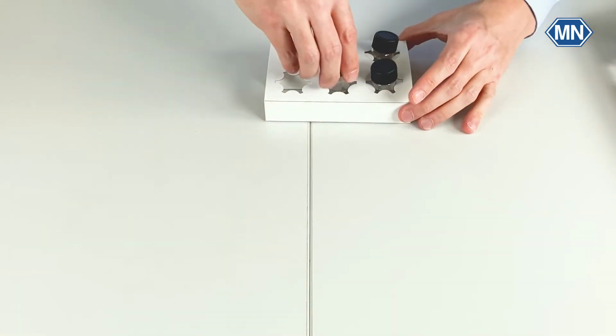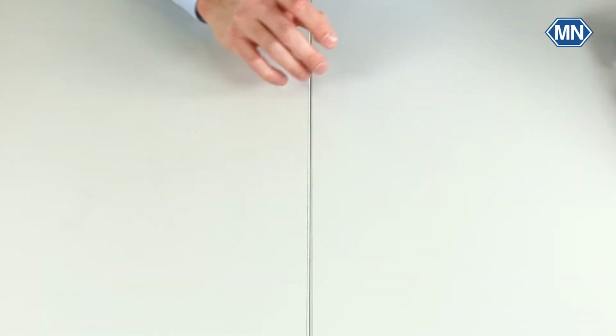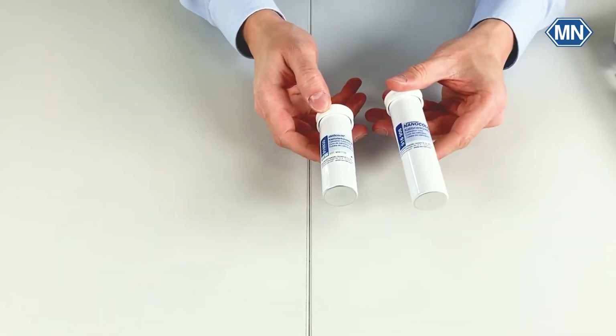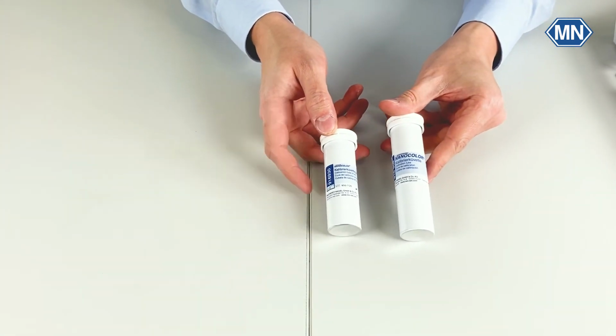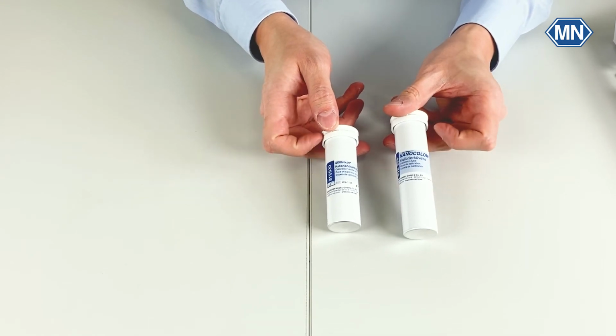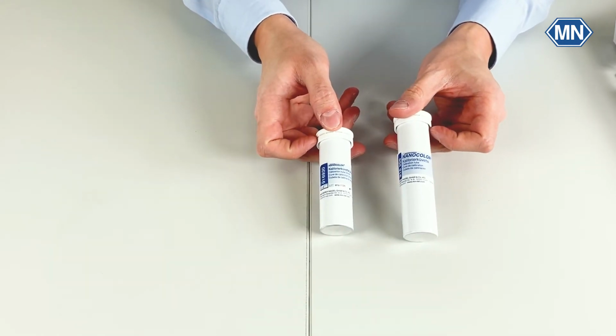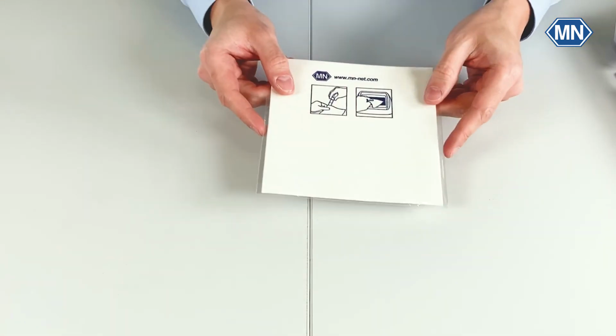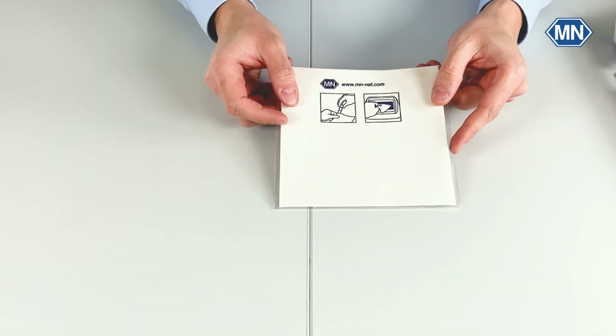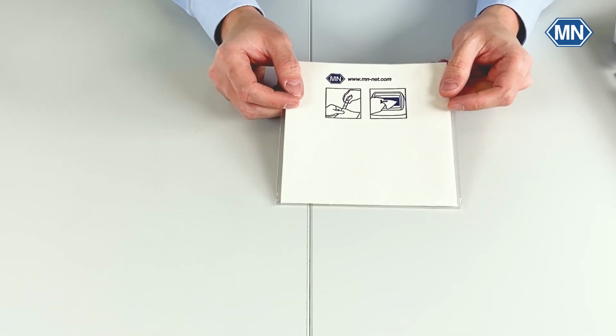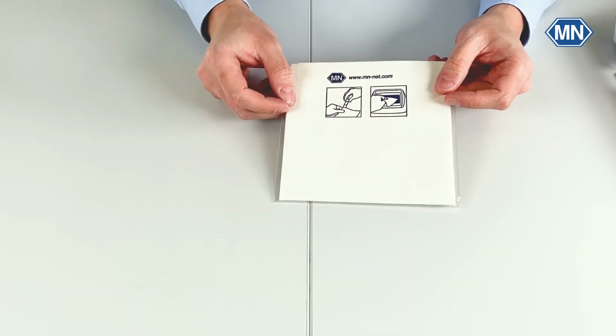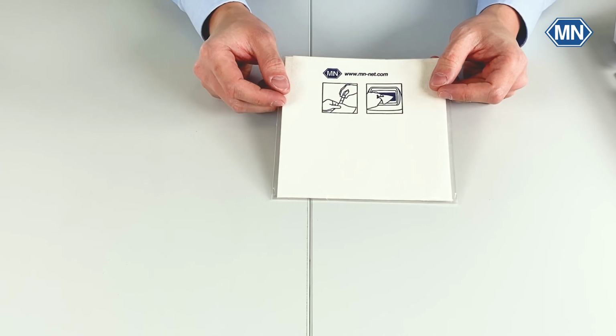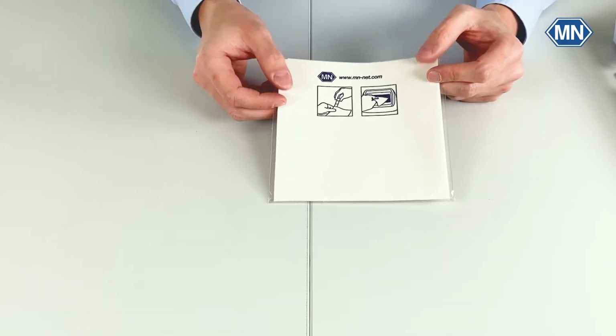As with our other photometers, you don't need to send the Nanocolor Advance in for calibration. Just use the 2 calibration tubes for the 24 and 16mm round tubes and calibrate the photometer yourself. Please make sure that the cuvettes you're using and also the calibration tubes are always free of scratches, dust and grease. For this, use the special lint-free cloth, which can also be used to clean the display of the device.